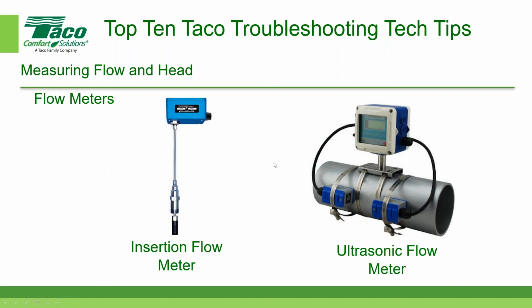They usually need about 15 pipe diameters at the inlet and about 10 pipe diameters at the outlet to get an accurate reading. We run into that from time to time, where somebody will come along and say, well, we have this flow data, and your pump is pumping 20% less than what it should be, and we're proving that with the flow meter. And then I get the photographs and I realize that they connected the ultrasonic flow meter on an elbow. So the flow comes vertically upward, makes a 90-degree turn, goes right into the flow meter, and then they have a valve at the discharge side of the flow meter that's throttled back. You can't get good readings with those kinds of field conditions. So it's important to know what the limitations are of the instrumentation.